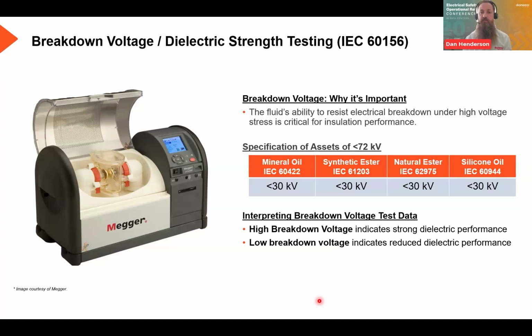But once you start getting down towards your nominal voltage, you've got that massive increased risk of, well, it's not an insulator anymore. It's going to conduct, so you're straight into that flashover territory. So it's such an important thing to make sure what testing you are doing is against a recognized standard, or at least the standard for your geographical location.